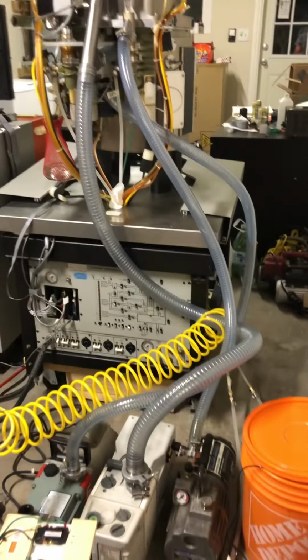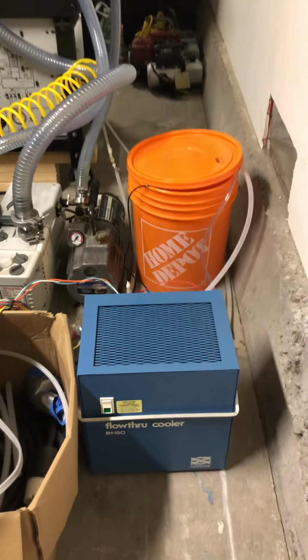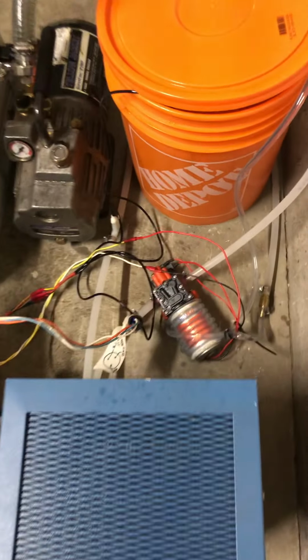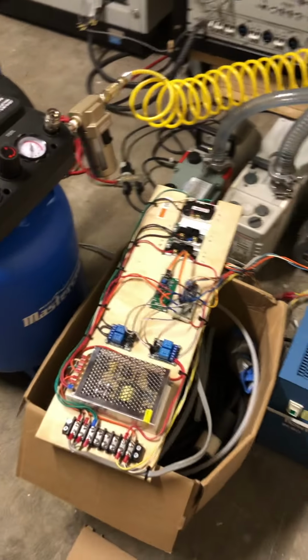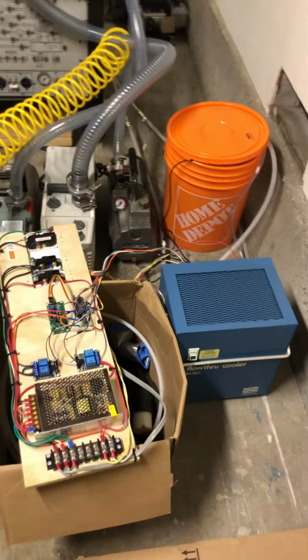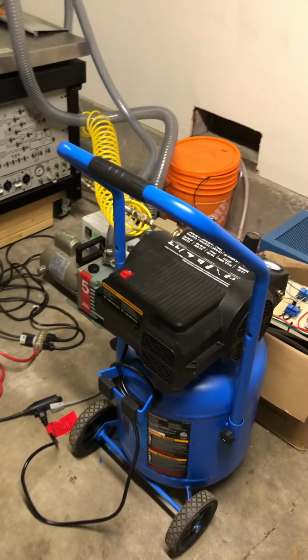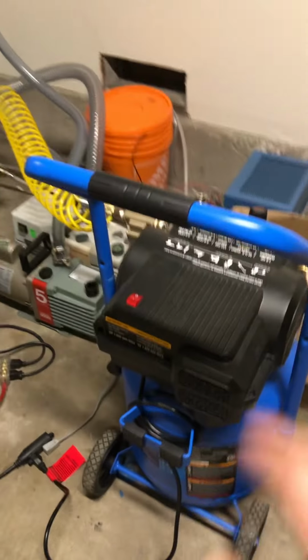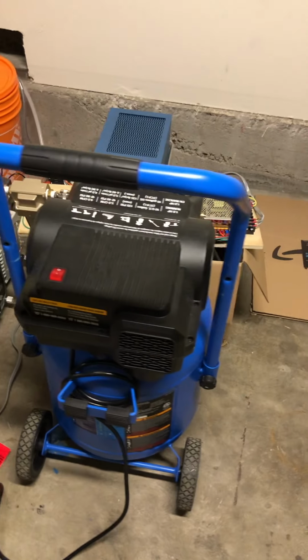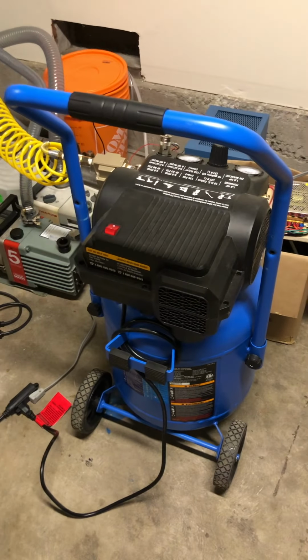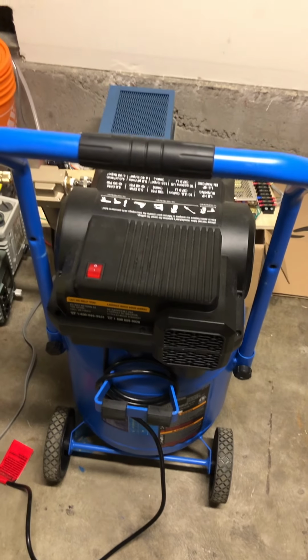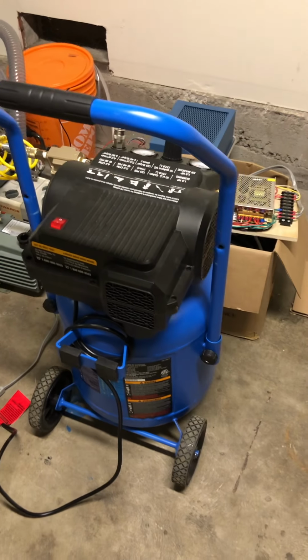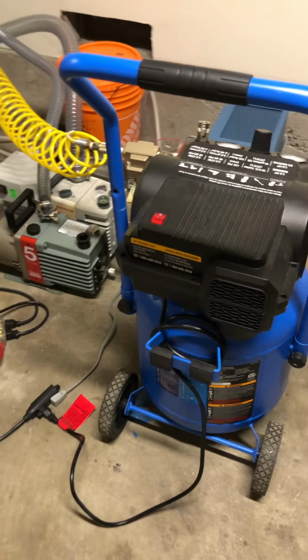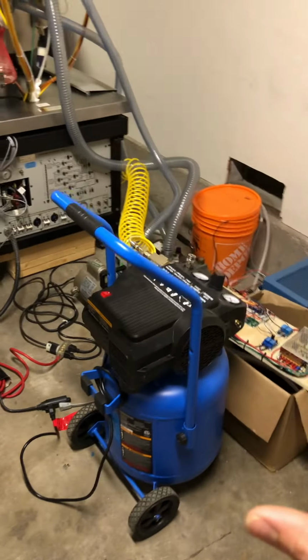The cooling water for those pumps is supplied by this water chiller. This chiller, plus the water pump and the control circuit, takes another 300 to 400 watts. But by far the most power hungry device is this air compressor. Fortunately, this thing doesn't always have to run. It's maybe only on 10% of the time. But when it is running, it's a 12 amp, 120 volt motor. So that's another 1400 watts. So that kind of is the bulk of the power.